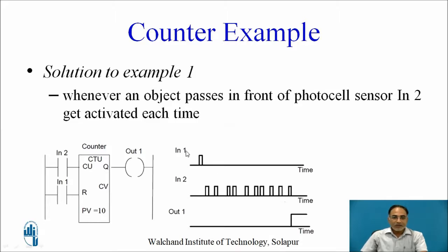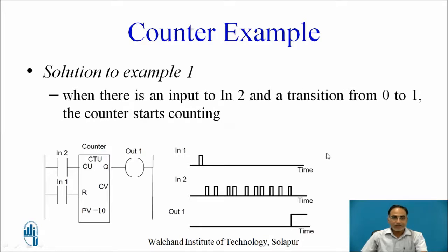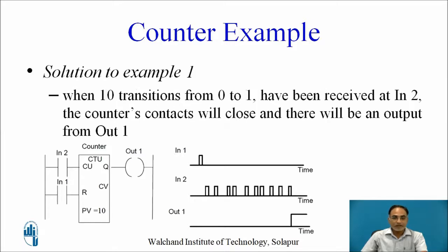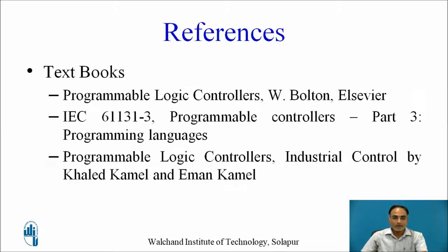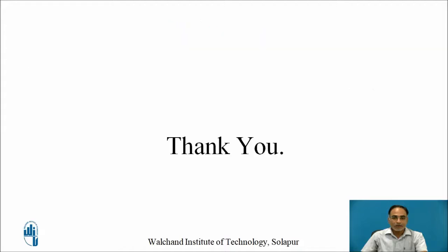In summary: whenever an object passes in front of the photocell sensor, input 2 gets activated. Each time there is a transition from 0 to 1 at input 2, the counter starts counting. After 10 such transitions, the counter contact closes and there is an output from output 1. These are the references for further reading. Thank you.